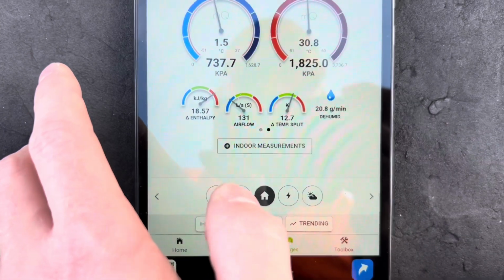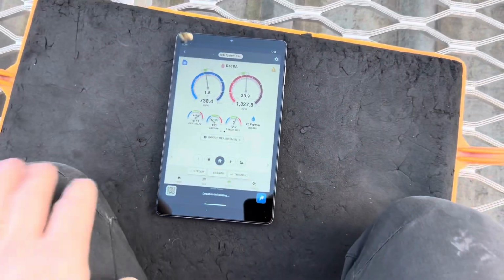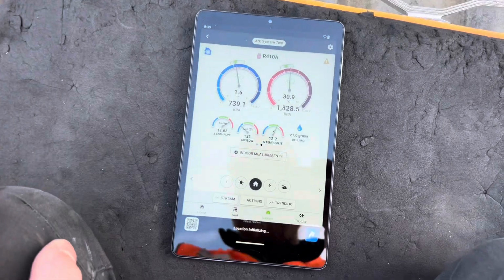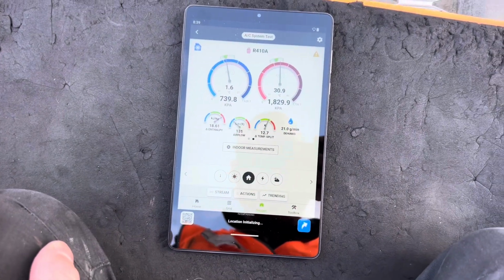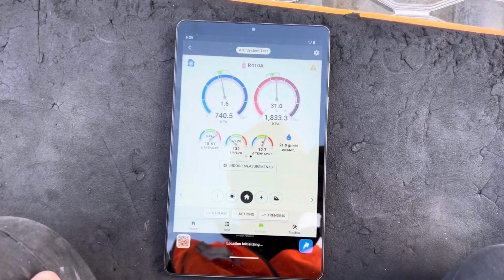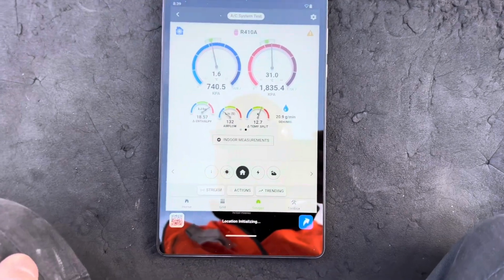Temp split 12.7, that's a hell of a lot better than what it was. I was testing in heat mode when I flagged the issue, so it usually operates a bit higher than that, but 12.7 in cooling is pretty good for me.